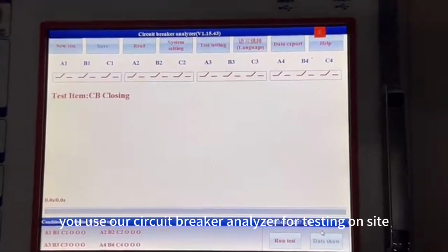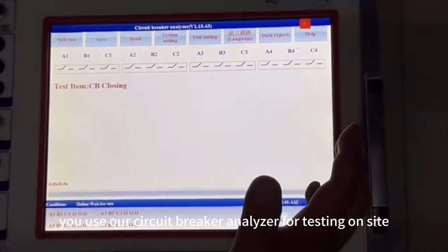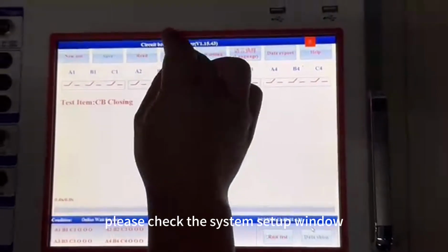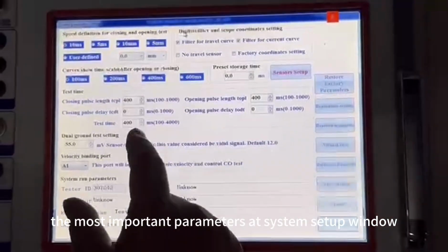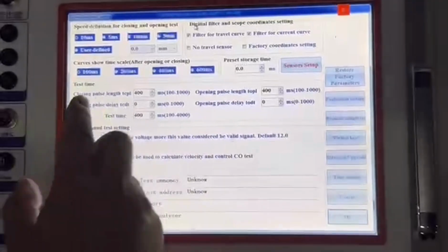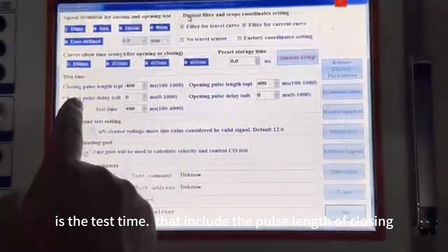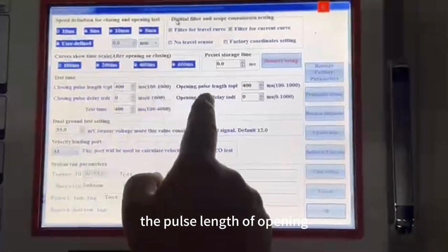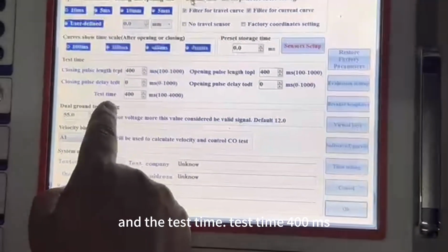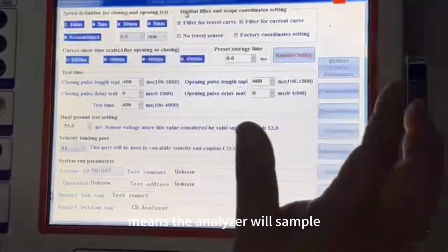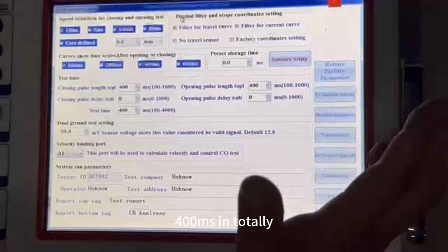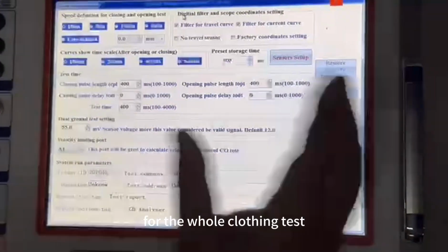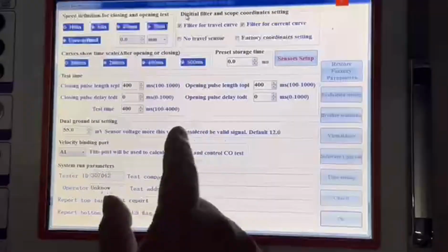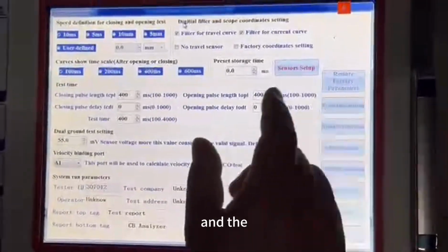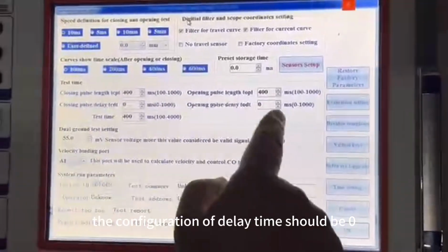If this is the first time you use our circuit breaker analyzer for testing on site, please check the system setup window. The most important parameters in the system setup window are the test time, including the pulse length of closing, pulse length of opening, and the test time. Test time 400 milliseconds means the analyzer will sample 400 milliseconds in total for the whole closing test. And the configuration of delay time should be 0.